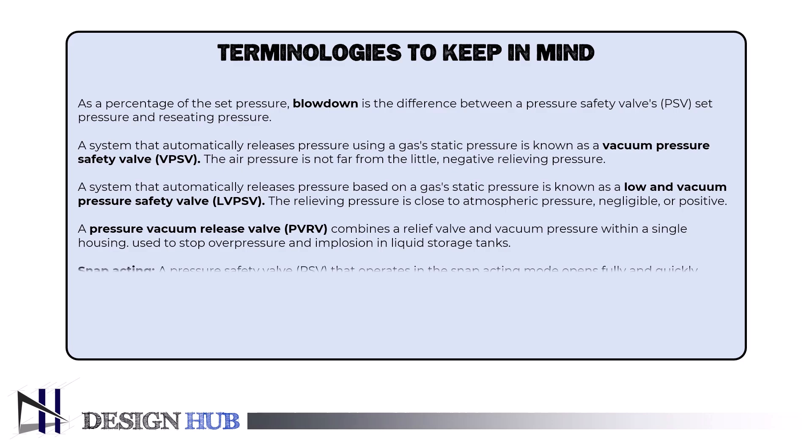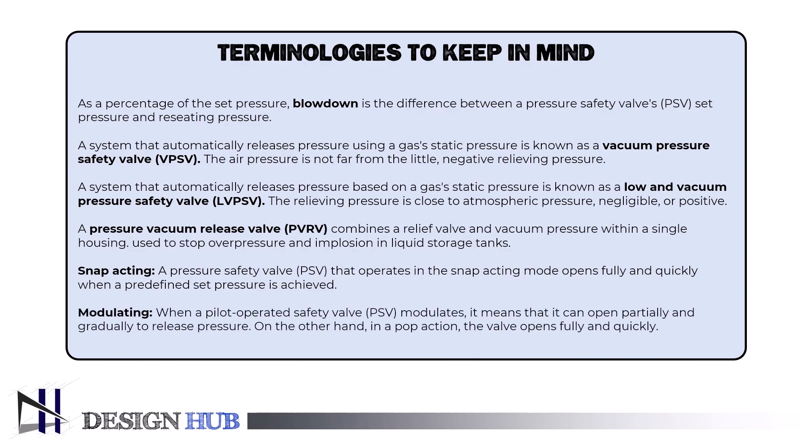The eleventh is a pressure safety valve, PSV, that operates in snap acting mode and opens fully and quickly when a predefined set pressure is achieved. The twelfth is modulating: when a pilot-operated PSV modulates, it can open partially and gradually to release pressure. On the other hand, in a pop action, the valve opens fully and quickly. These terminologies are very important if we are dealing with safety valves.